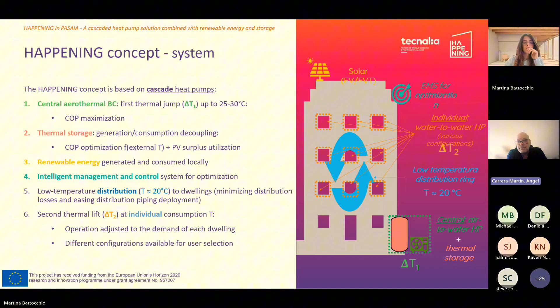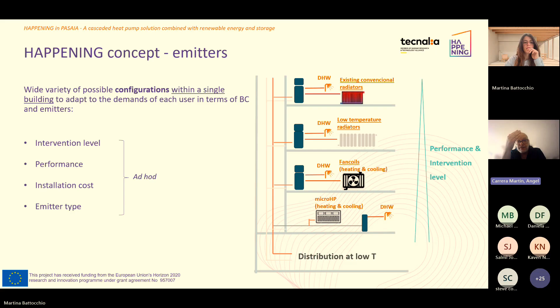In the project there were three demos, and each used a different approach to these cascade heat pump systems. Some solutions have micro heat pumps using fan coils directly connected to the distribution loop, meaning direct expansion fan coils.